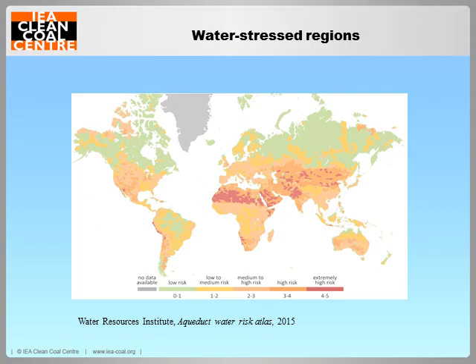For example, last year a number of power plants in India had to temporarily shut down due to a lack of water. And this included all 5 units at the 1600 megawatt Farakka coal-fired power plant in West Bengal. And the power plants in the northeast region of the USA, where water is actually abundant, are facing issues of water quality and temperature. Power plants here have had to close down at times to ensure they do not exceed the permitted water discharge temperature. So the number of power plants affected is likely to increase in the future, especially with the growing energy demand in many parts of the world. Consequently, the pressure on power plant operators to conserve water will increase.